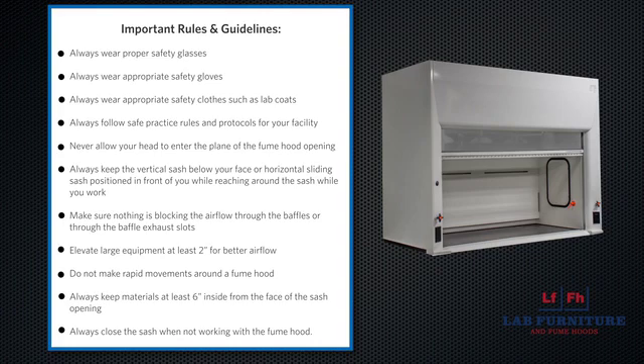Make sure that nothing is blocking the airflow through the baffles or through the baffle exhaust slots. Elevate all large equipment at least 2 inches for better airflow. Do not make rapid movements around a fume hood.